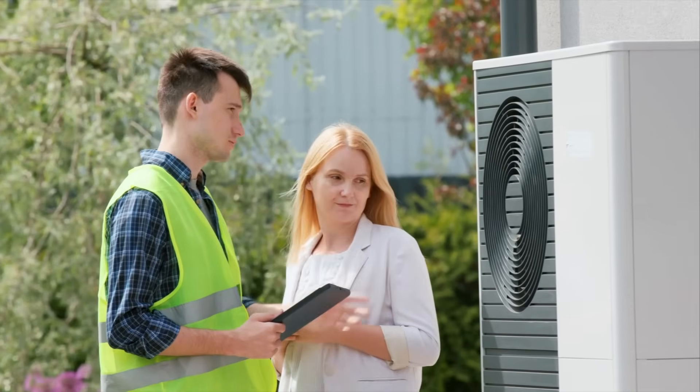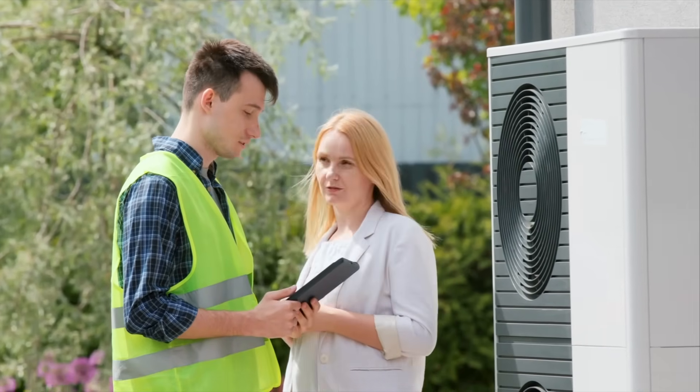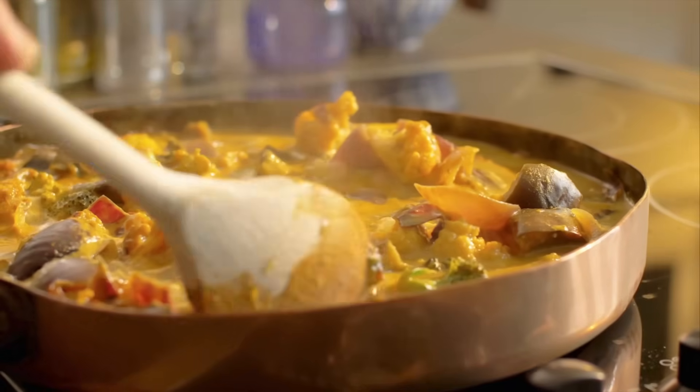So why is this set so poorly so often? Curves are frequently set once on the installation day and then never revisited. Sometimes they're based on calculations, sometimes on the installer's habit, but rarely are they based on how the house actually behaves once people are living in it. And as I've said countless times across these videos, real homes don't match calculations — they have drafts, sunlight, cooking, people.